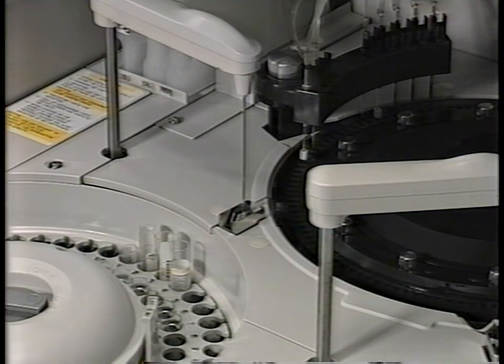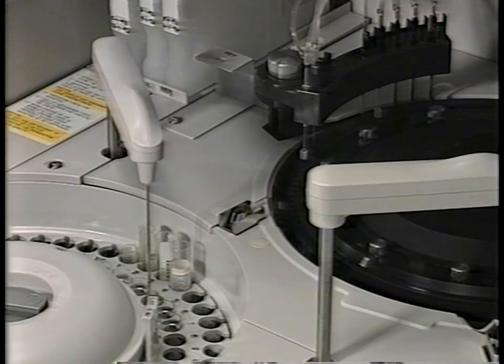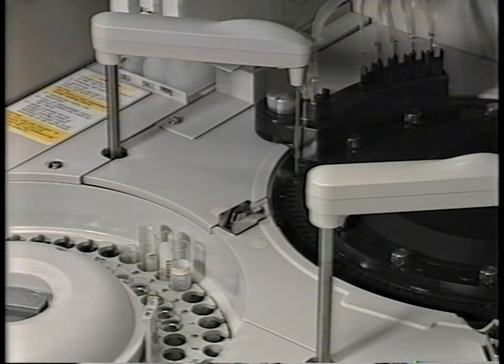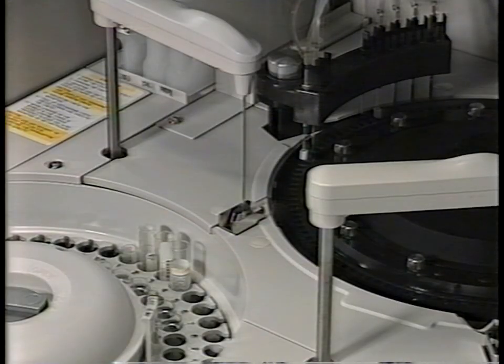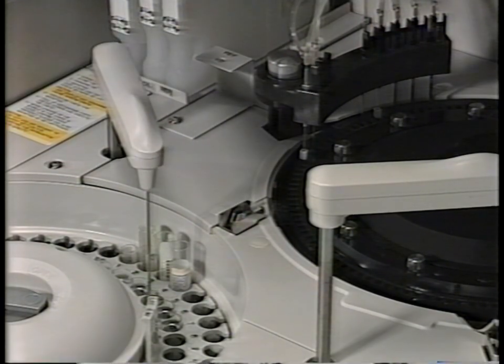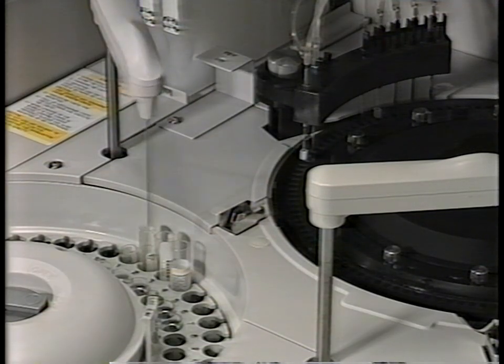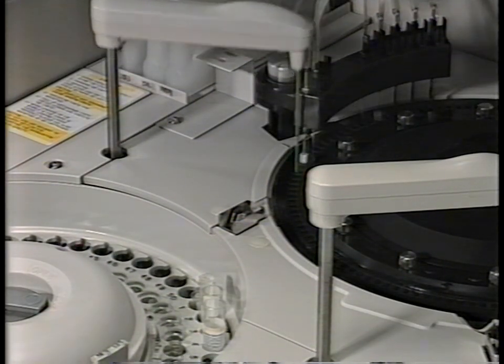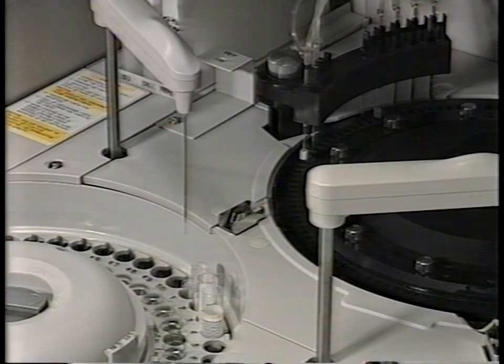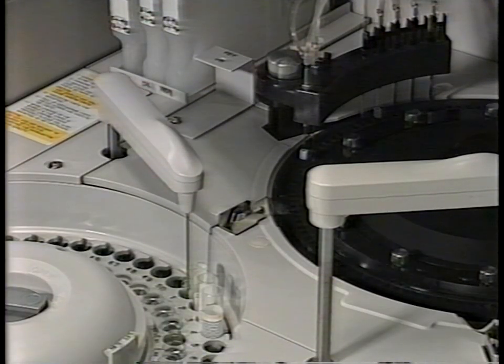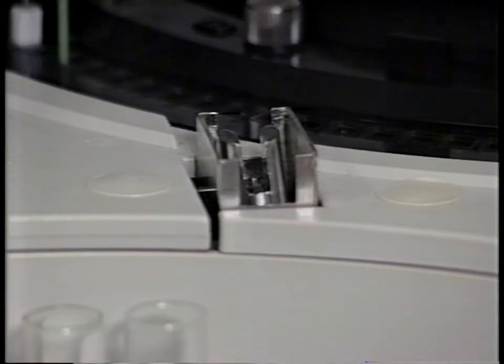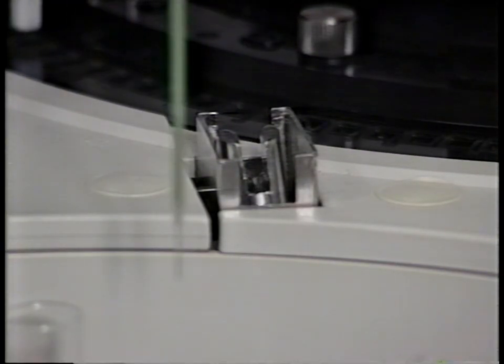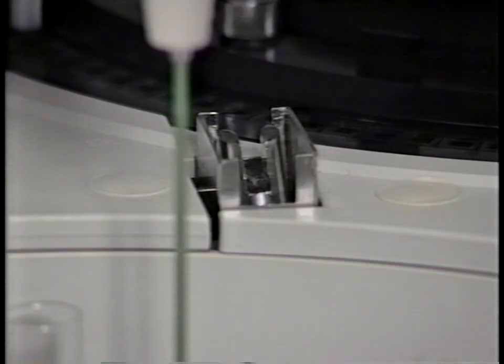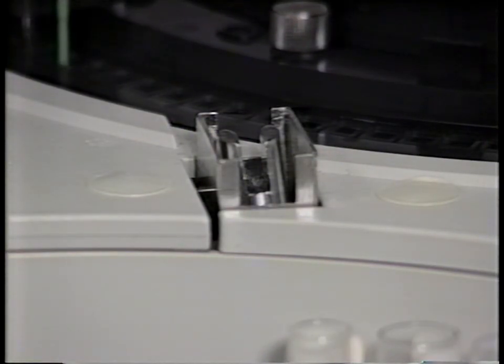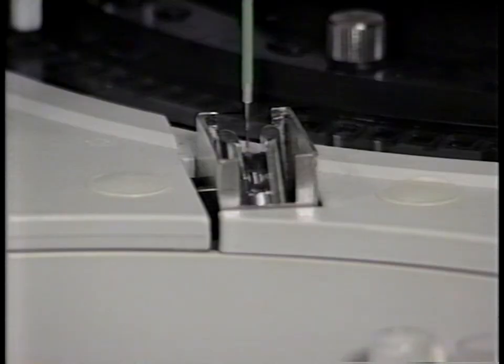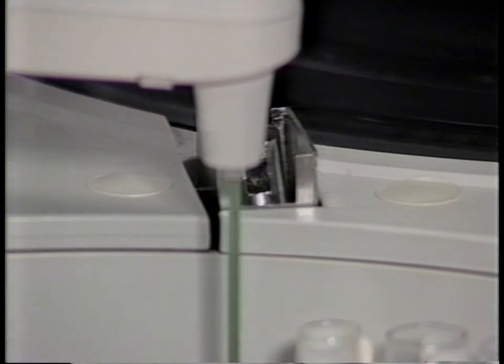The sample probe also serves as a liquid level sensor. When sensing liquid in a sample cup or tube, the vertical descent positioning of the probes in the sample can be controlled. This ensures proper pipetting without overexposing the probe's outer surfaces to the sample. If the probe encounters an obstruction during a descent, an abnormal descent sensor is triggered. This sensor prevents damage to the probe. This controlled descent, along with internal and external probe washes, maximizes accuracy and precision. After the sample is aspirated, the probe moves over the cells of the reaction disc to dispense it into a cell.